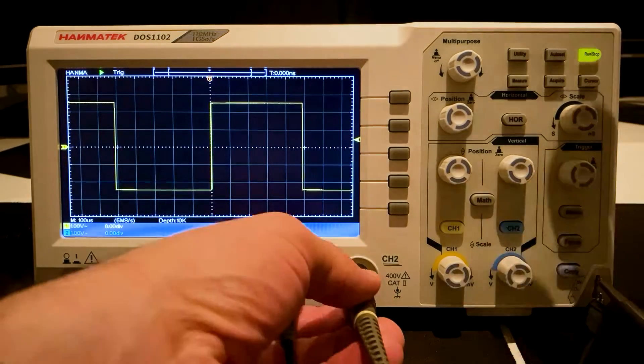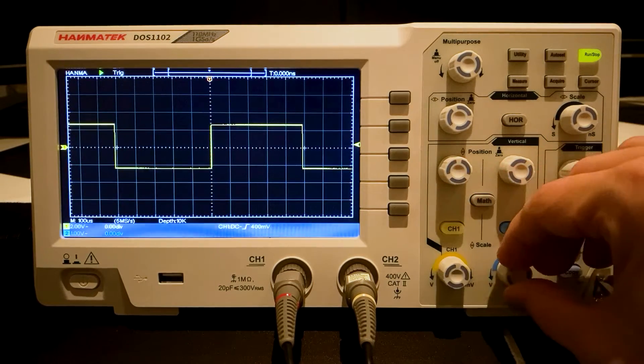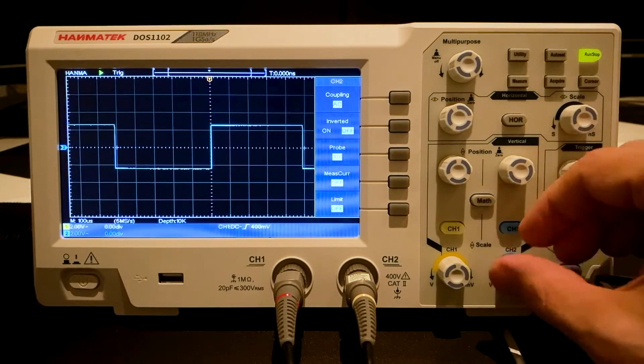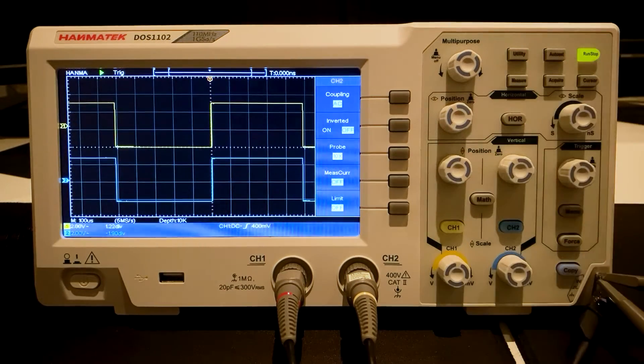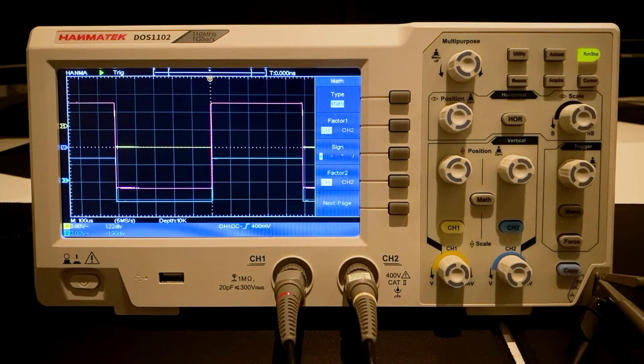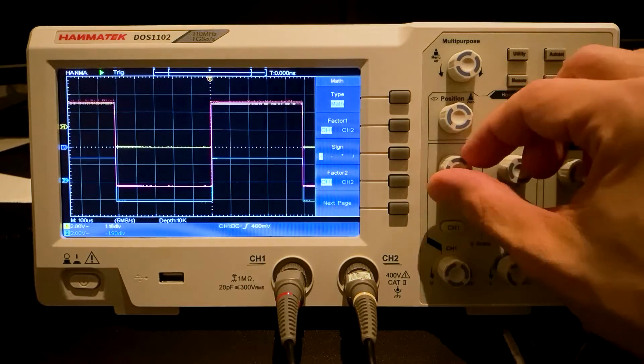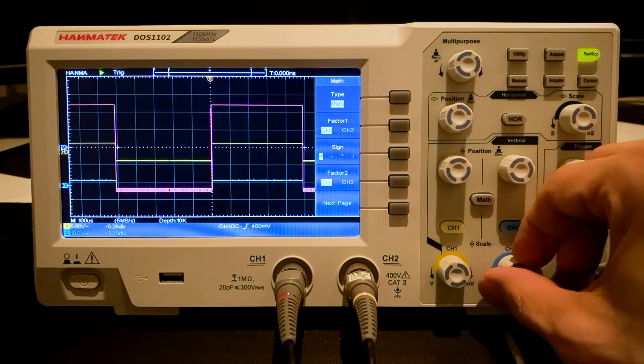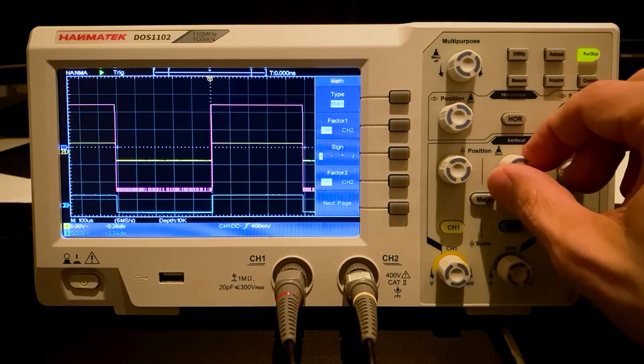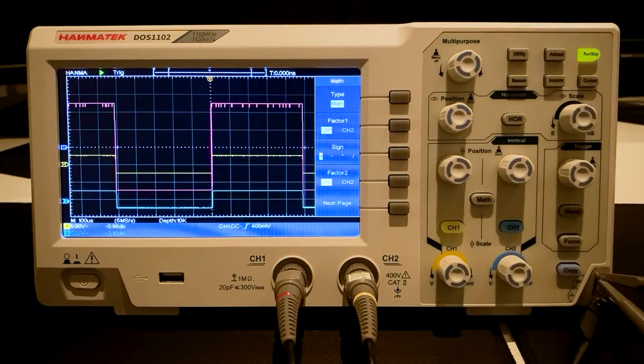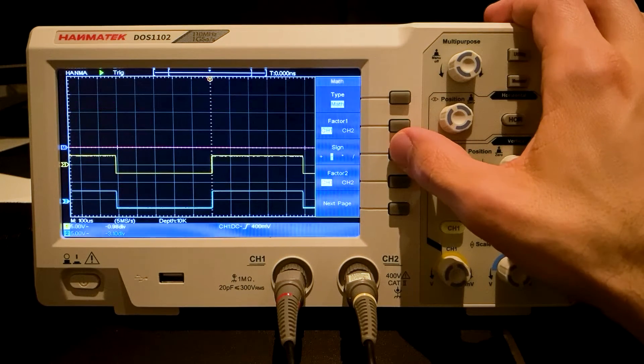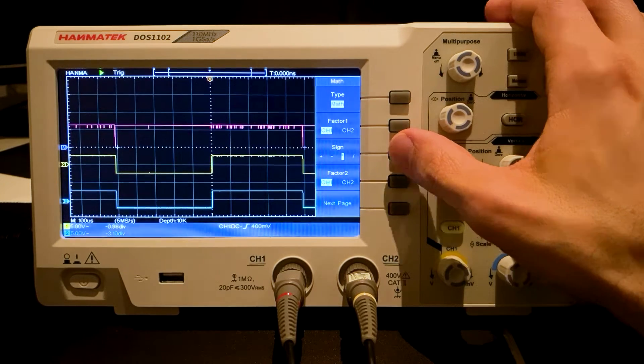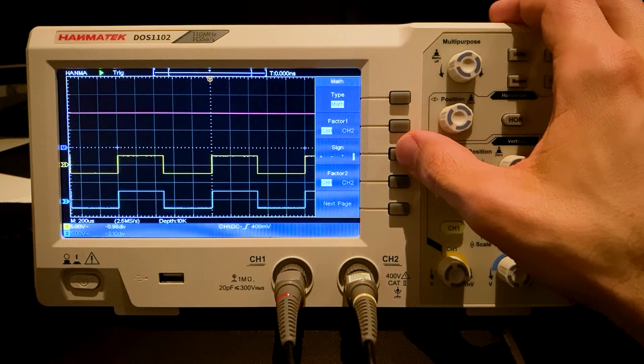With the Math function, mathematical operations can be applied to the signal. Another signal is required for the test. Two signals from Channel 1 and Channel 2 are aligned with one another. The Math function is opened by pressing the grey Math button. A third signal is generated on the display. The signal is the sum of Channel 1 and Channel 2 because the plus symbol is selected under Sign. The minus operation is chosen. A straight line is created at zero point. The other operations, multiplications and divisions are tested. The top signal changes.